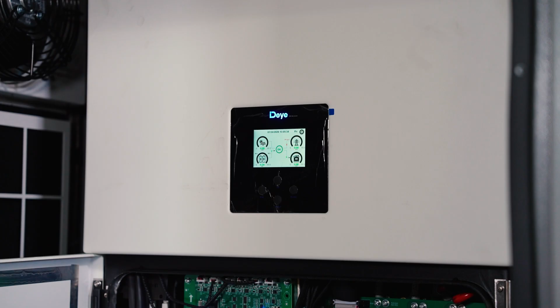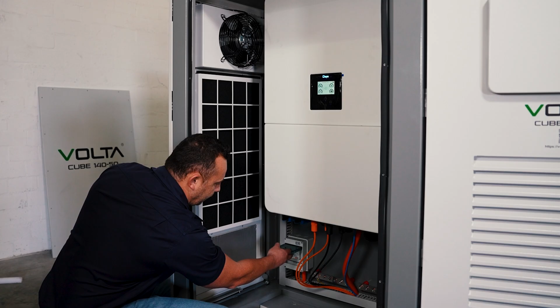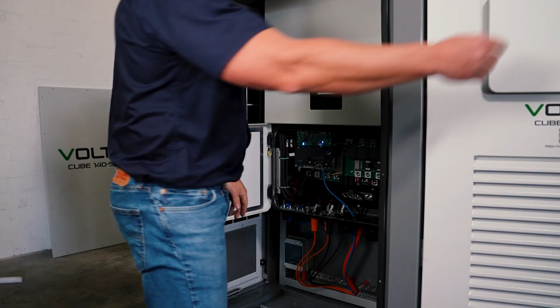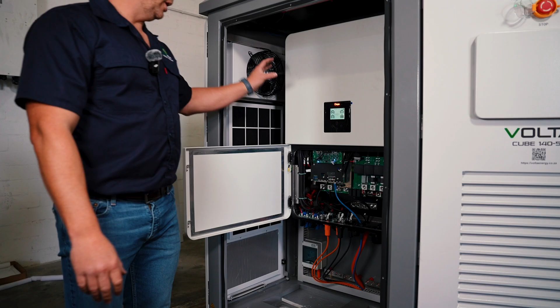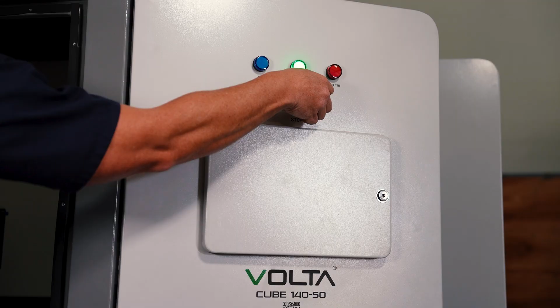Alright guys, so now you can see your system is on. You can close your door. At your bottom left, you'll see there's an earth leakage. That's to power your aircon. At the back, in this current state, your aircon is on. Now, like I explained earlier on, this is your emergency stop. If you press your emergency stop, your input, output, everything will not work. That means your inverter is safe, there will be no power in the property. To get it out of that state, you'll see an F22 error. It will clear in 1 minute, then the system will operate as normal.